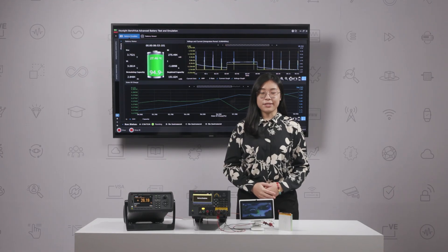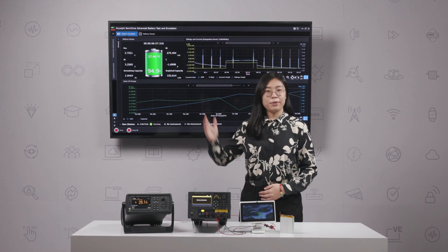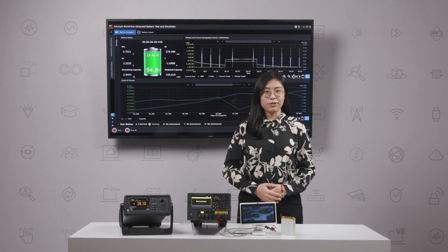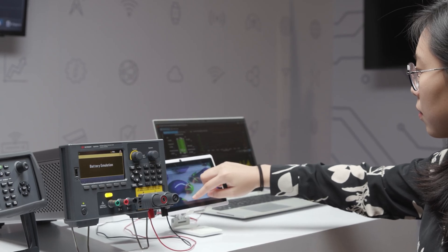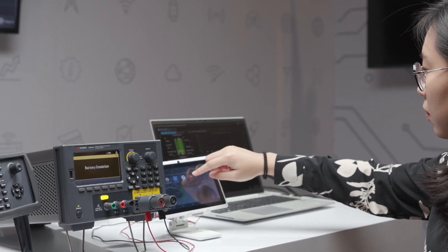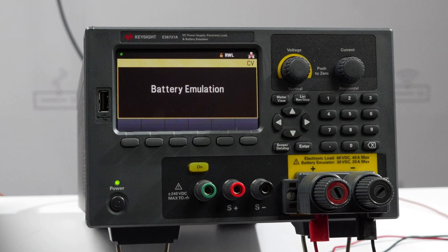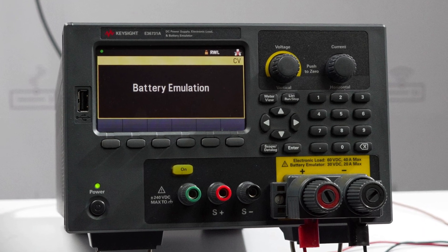Once a battery model is created, the E36731A paired with the BV9210B can be used to emulate the battery to power up any IoT or mobile device without needing a physical battery. By repeatedly testing a physical battery under high usage conditions, it may cause overheating of the actual battery. The emulation mode of the E36731A helps to address this issue.